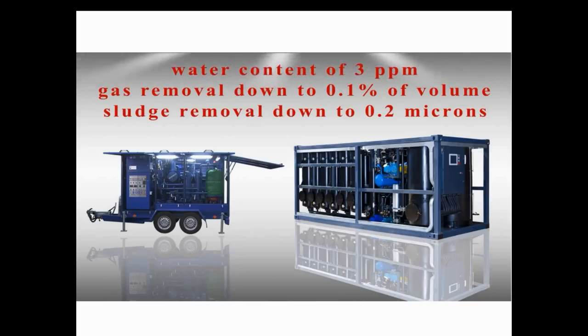However, the reason for such tight specifications is that transformers have become much smaller at the same amount of power. So the oil and the paper and the dielectrics have to work much harder to retain insulating properties in a transformer. Both stationary and mobile plants are effective and easy to operate.